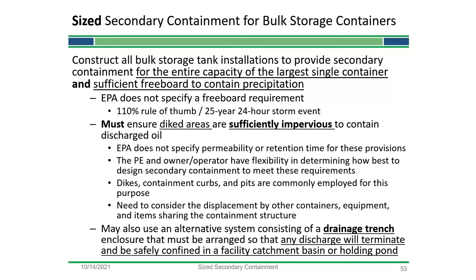And if the secondary containment area contains additional tanks, piping, support structures, then calculations for the size secondary containment volumes must take into account displacement from these other items sharing space within the containment structure. Facilities may also choose to use an alternative system consisting of a drainage trench enclosure to meet the size secondary containment requirement, provided that this enclosure is arranged so that any discharge will be safely confined in a facility catchment basin or holding pond.